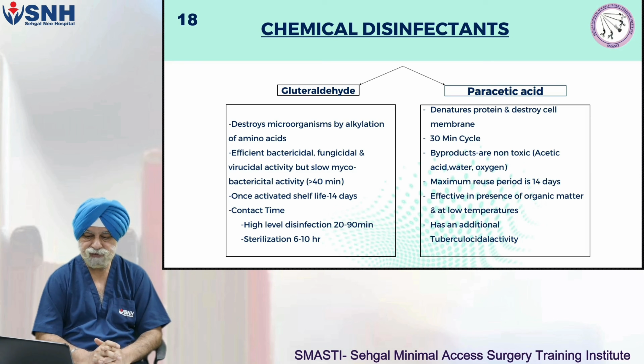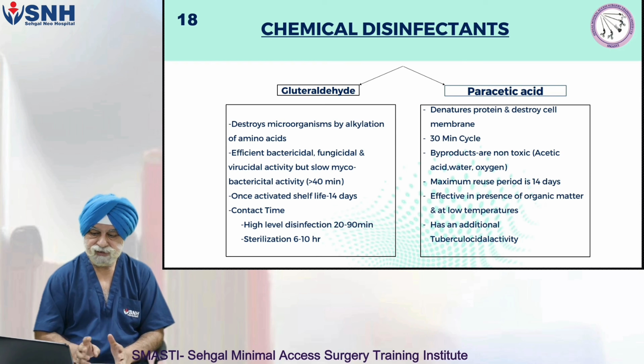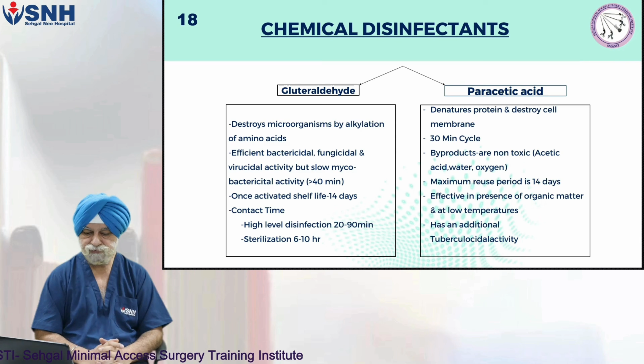Okay, but it has a very slow mycobacterial bactericidal activity. Okay, and I've already discussed with you that once activated, the shelf life of the glutaraldehyde is 14 days. Now the contact time, if we are doing high level disinfection of the instruments, should be between 20 to 30 minutes. Although some products recommend even up to 90 minutes, within 20 to 30 minutes the instruments are disinfected up to the high level disinfection.